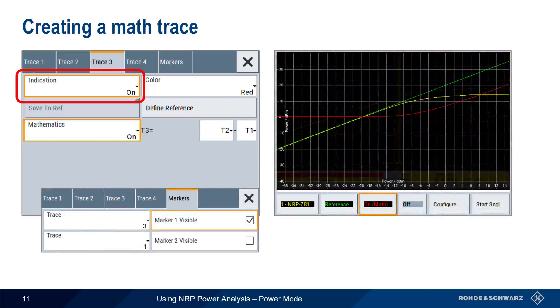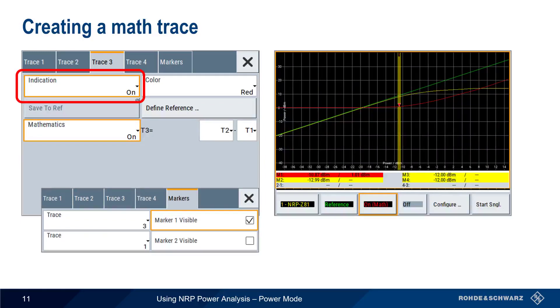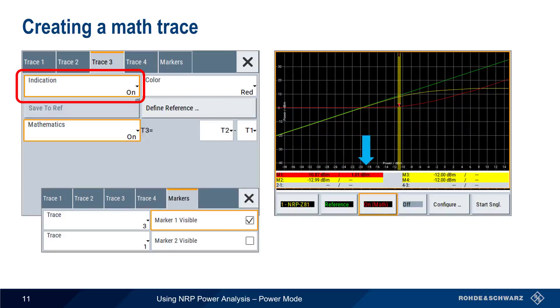By placing a marker on trace 3, we can easily read off the input power that corresponds to the 1 dB compression point.